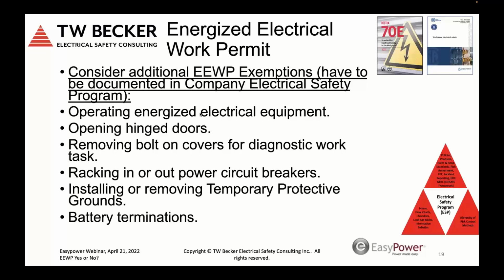How do I establish an electrically safe work condition if I don't operate electrical equipment, then rack the power circuit breakers in and out, and for high voltage install temporary protective grounds? The permit becomes purely bureaucratic.